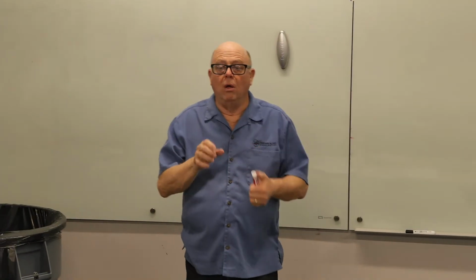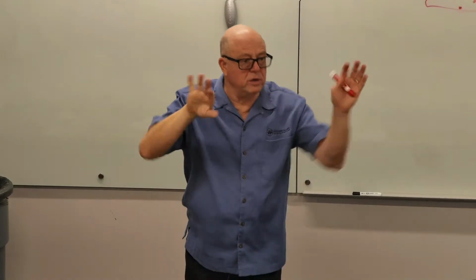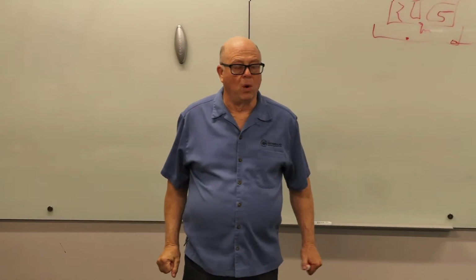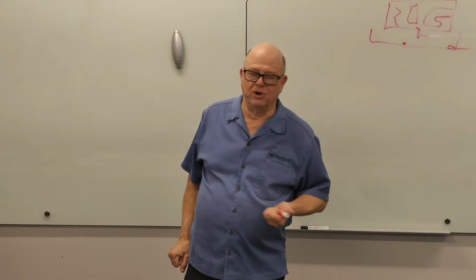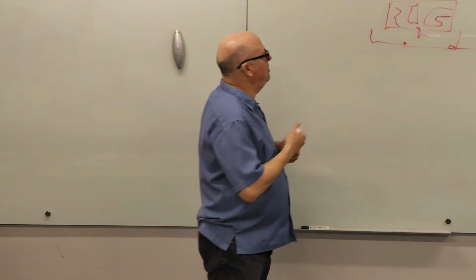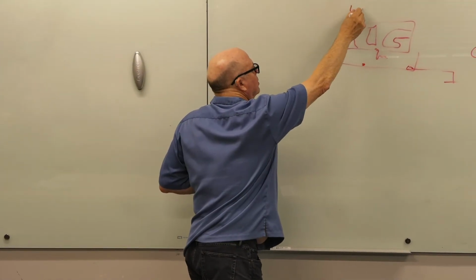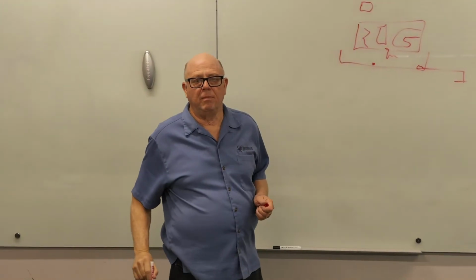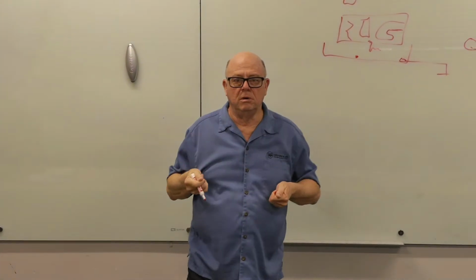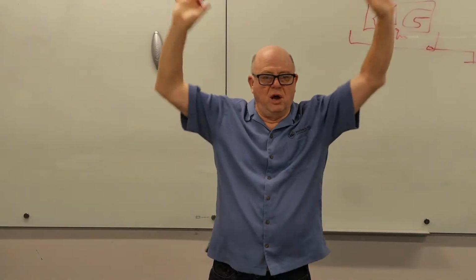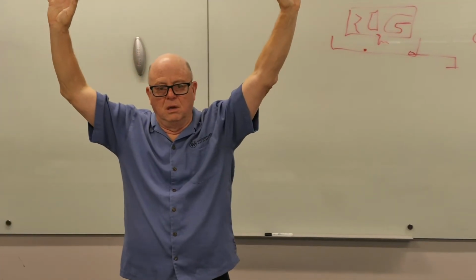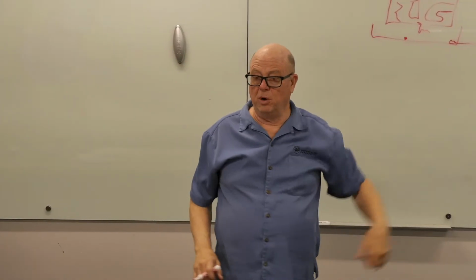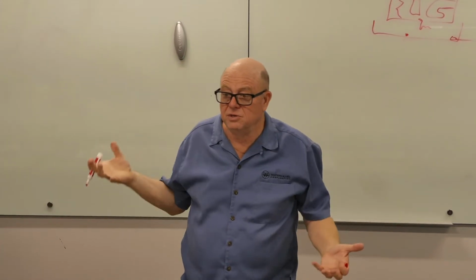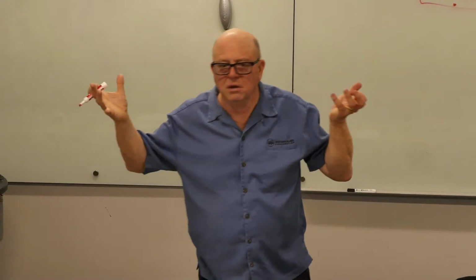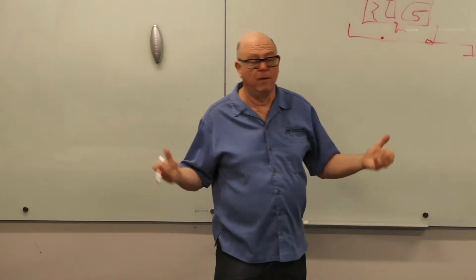Okay. That button, the way it works, if it comes in contact with water, it closes a circuit. Or opens a circuit. And there will be, on the little control board for this little thing, terminals to hook it to, that when it gets moisture, it cuts off the unit. And that's totally legit. It doesn't need to drip somewhere because people will start to complain because the unit is no longer cooling, right? Then you'll get a complaint, and then somebody will go investigate.